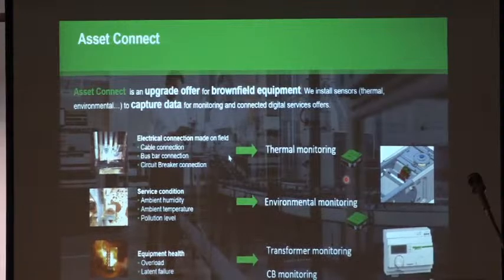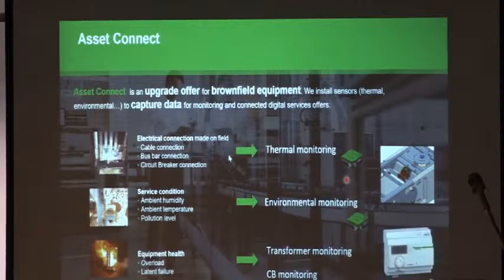We do this through battery-less sensors with an overall usage life of 25 years, taking information directly by connecting to the bus bar. This way we capture temperature information, and we have a similar connection to capture humidity information inside different areas, whether inside a cubicle or a whole electrical room. All this sensor information can be gathered by different products that communicate via Bluetooth or other technologies and feed it into our digital service platform.